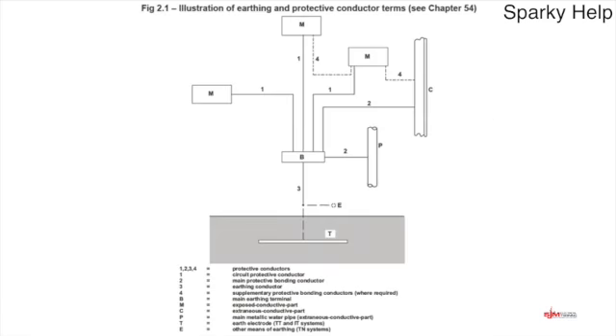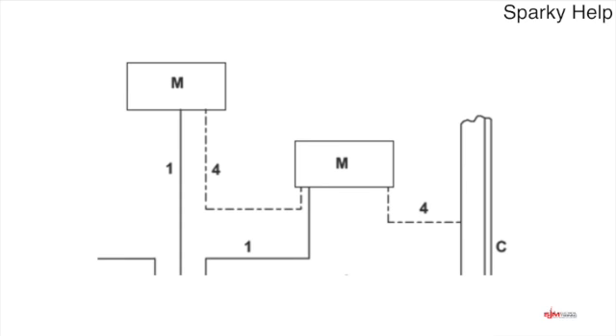Okay, and if we're not sure what M and C are, M is exposed conductive parts, and C is an extraneous conductive part. So M is exposed conductive parts. That's a piece of electrical equipment which has a metal case or earthing to it. And C is extraneous, so that could be a water pipe, structural steel, or something like that. And it's the sizing of conductors and the regulations that go with this.